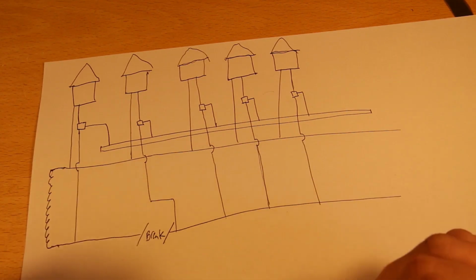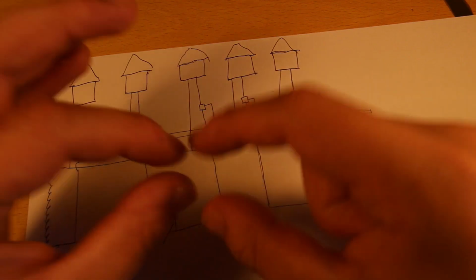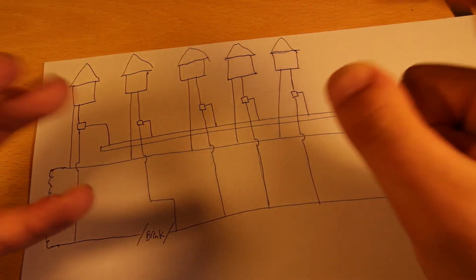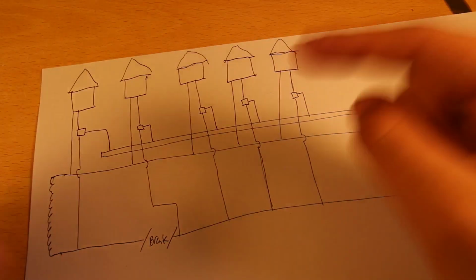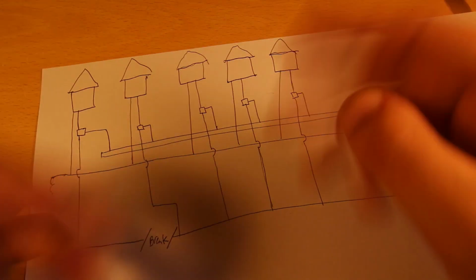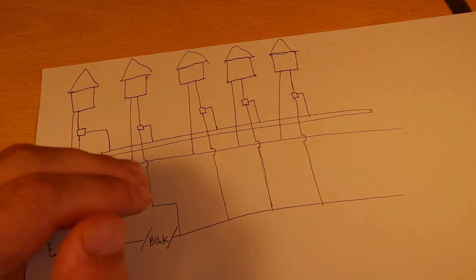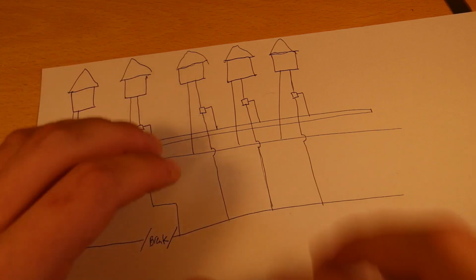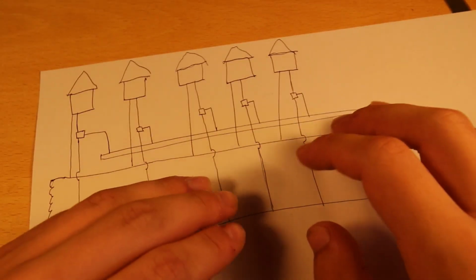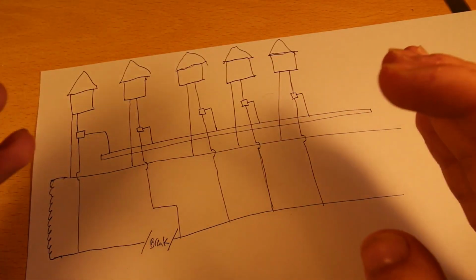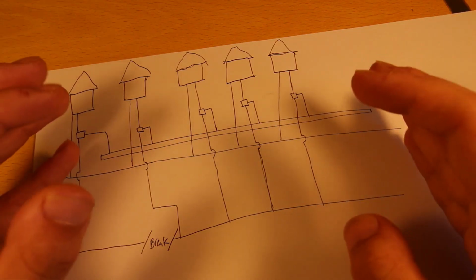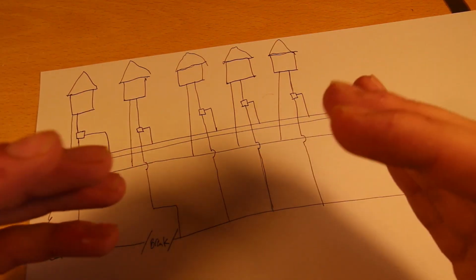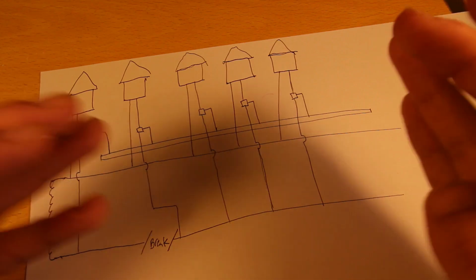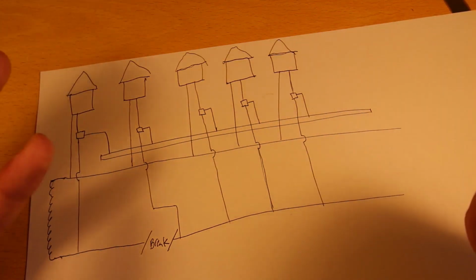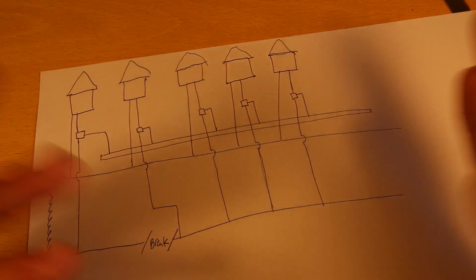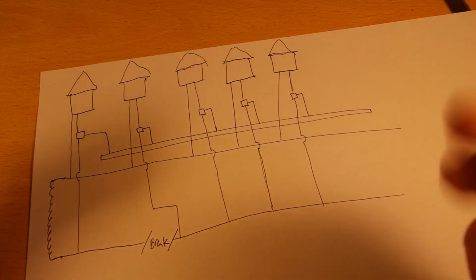In the US, I think they even have issues with the screen on cable TV sometimes, because they earth that at all the properties, taking diverted neutral currents through it. And this is the problem, because you're ending up with, in some cases, substantial neutral currents flowing through things that are never actually intended to carry a current at all, let alone potentially tens or hundreds of amps.